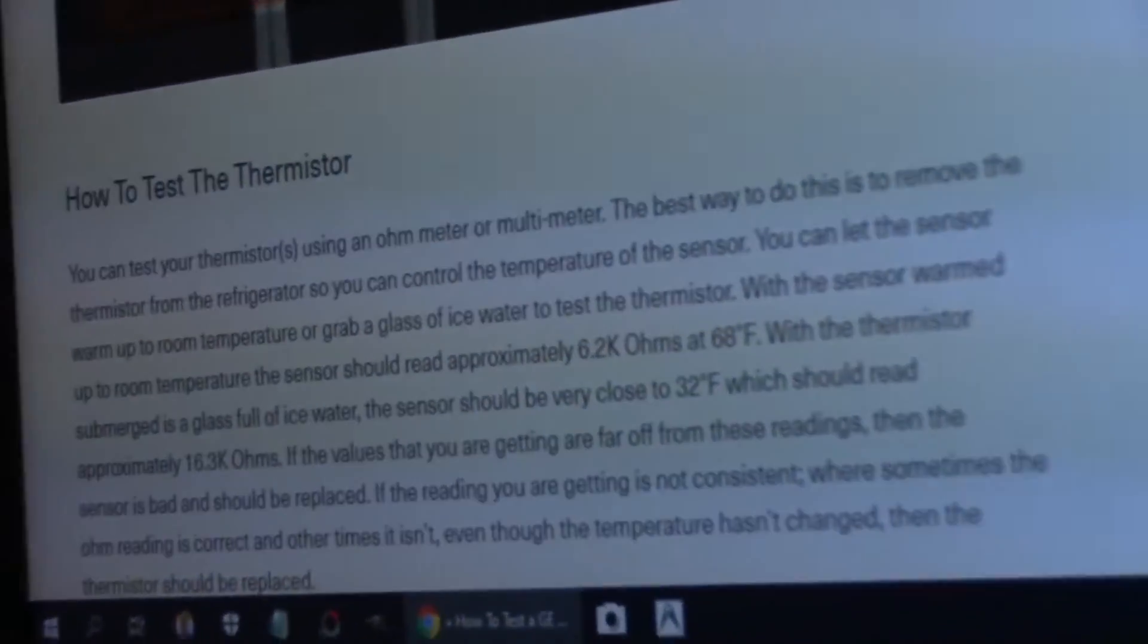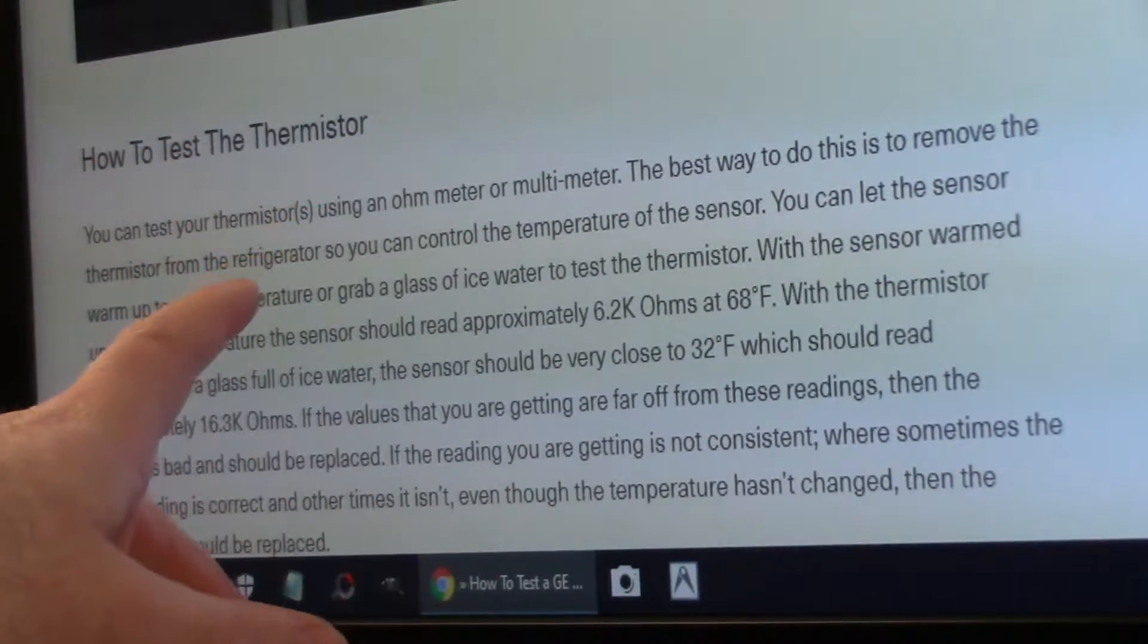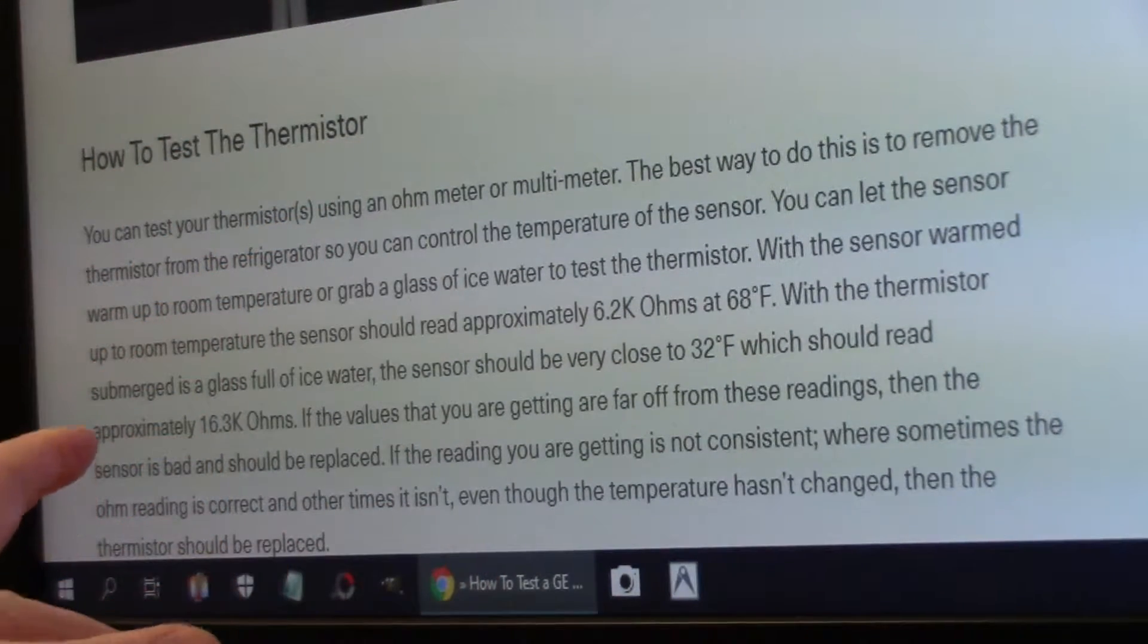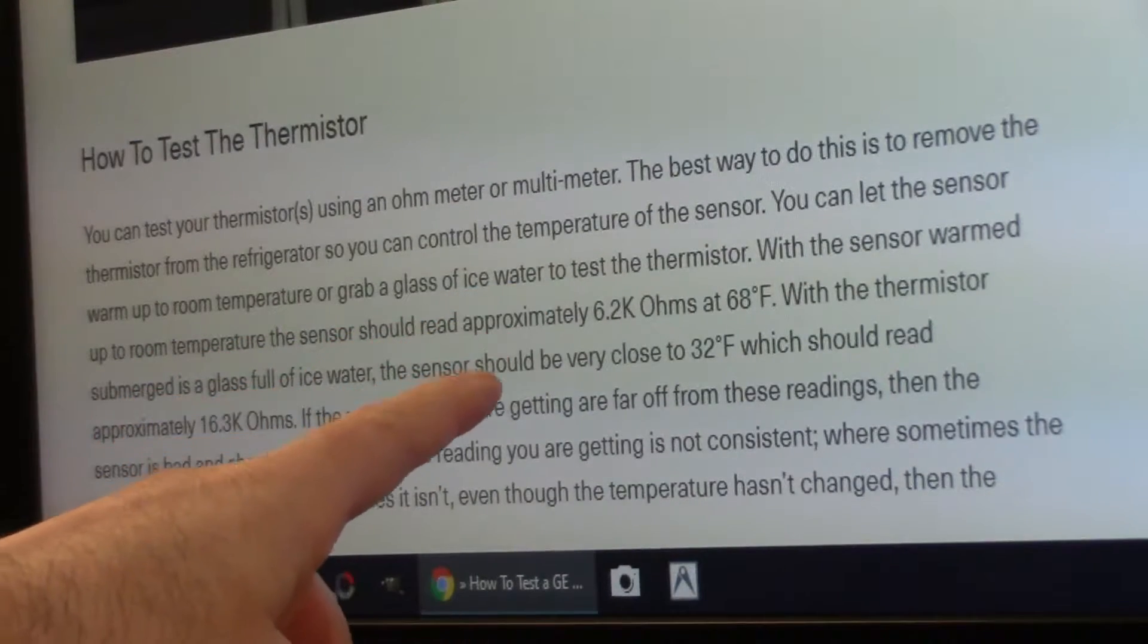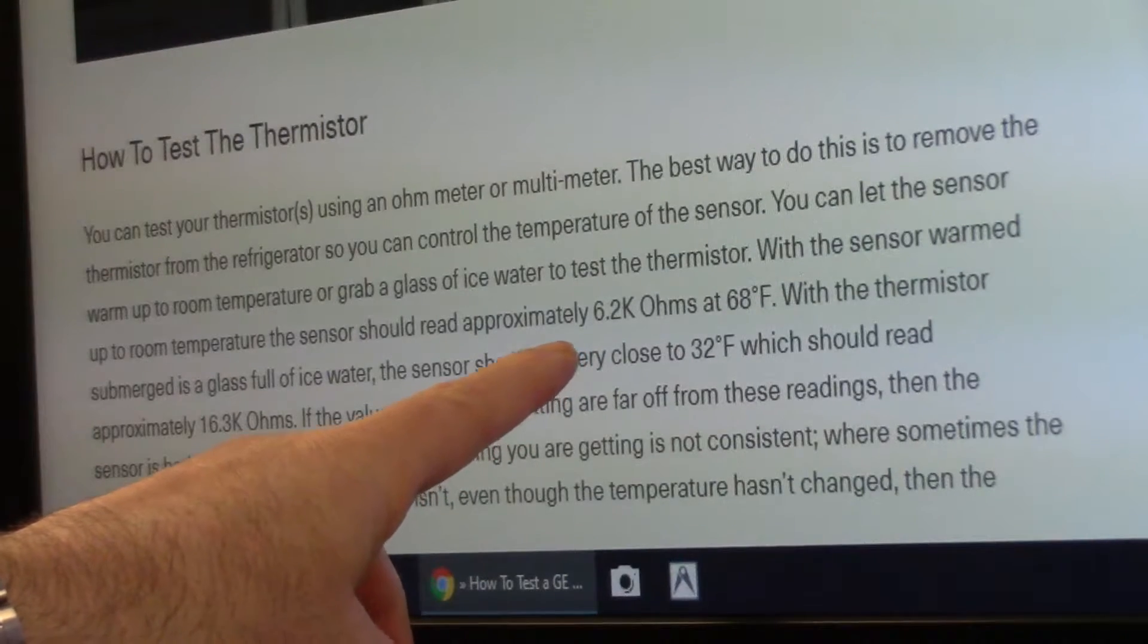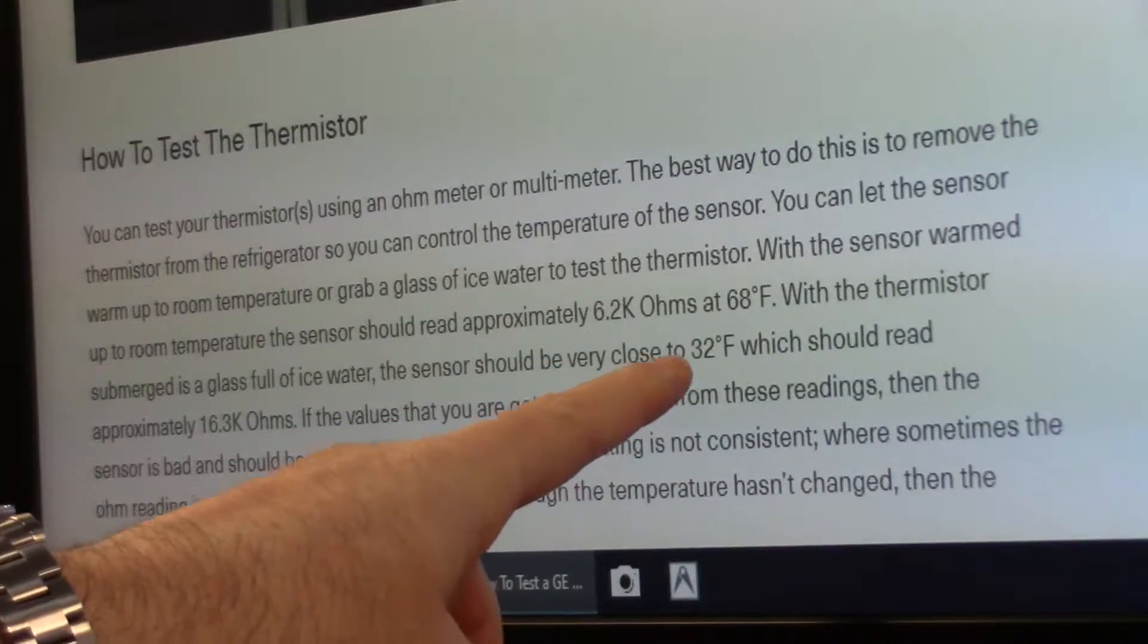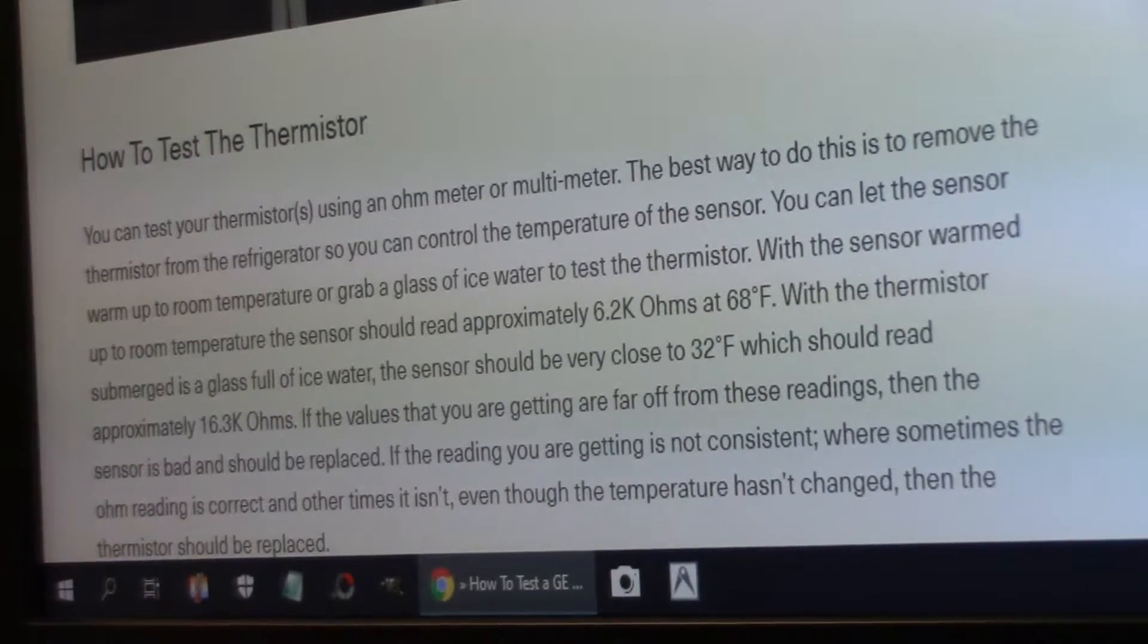Let's just look online here. I just did a Google search for GE temperature sensor testing and the site came up. At 68 Fahrenheit it should be reading about 6.2 kilo ohms and at freezing 32 Fahrenheit it should be reading 16.3 kilo ohms. So that's what we want to go by.